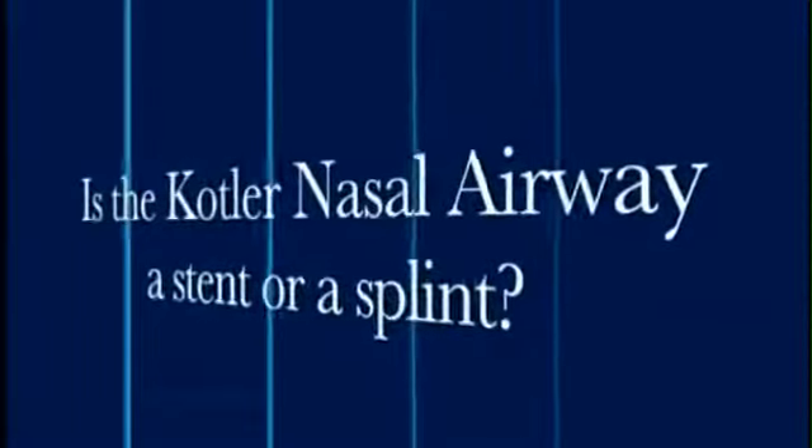Dr. Kotler, is the Kotler nasal airway a splint or a stent? It's neither. The airway is an airway — that's its major mission. However, due to its configuration, you can use it as a stent to help packing stay where you want it. For example, we put absorbable packing between the airway and the inferior turbinate after turbinate surgery. You can also put Telfa or any other major packing material between the airway and the septum. But the main mission is still providing a great continuous airway for the patient.